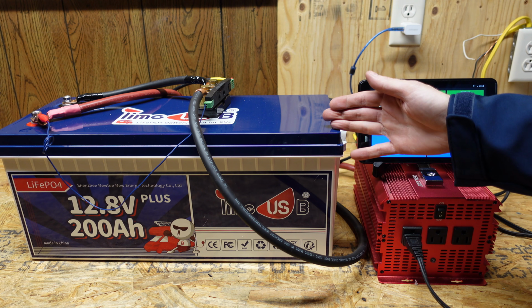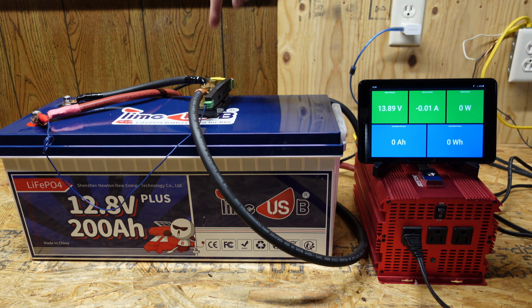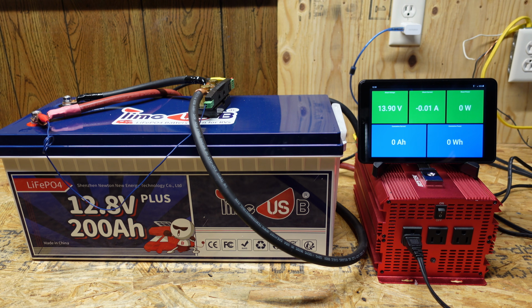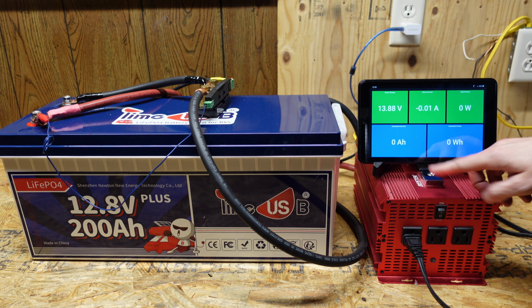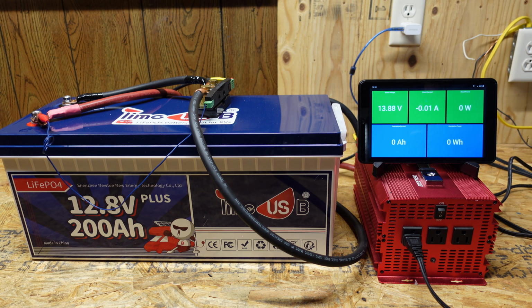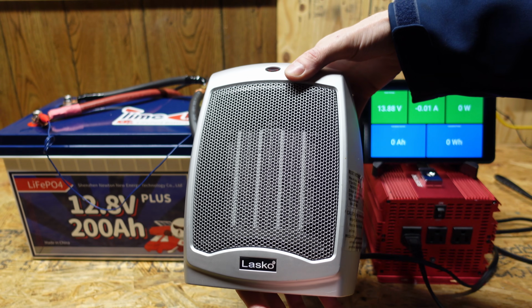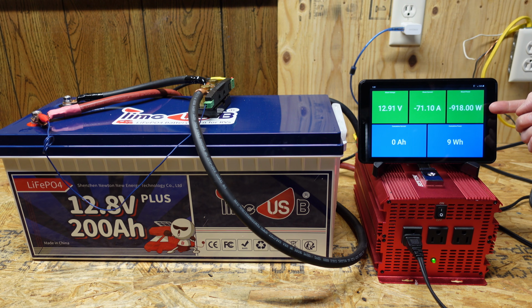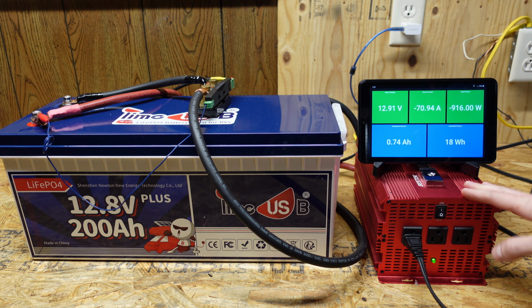This is the same typical capacity testing setup. We have a Batrium shunt, off camera back there, transmitting data to this display. We have the voltage, amperage, wattage, and the discharged amp hours and discharged watt hours. My test load will be this space heater here, and we're at approximately 918 watts, which is 70 amps at the current voltage. We'll leave this running until the BMS in our battery shuts down the test, and then we'll see our measured capacity.